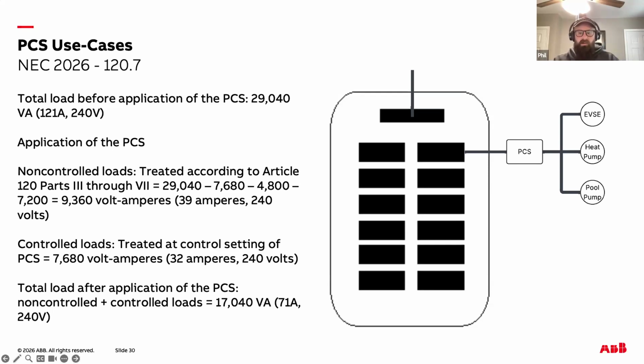Because the PCS is providing overload protection for this branch circuit, and per NEC requirements it cannot exceed 80% of the OCPD rating, the qualified person sets the PCS limit at 32 amps, which is 80% of the 40 ampere breaker. Since the PCS is monitoring only the controlled loads on this branch circuit, the NEC requires that these loads be represented in service load calculations using the PCS control setting rather than their individual nameplate ratings. As a result, the EVSE, pool pump, and HVAC heat pump are collectively treated as a 32 ampere controlled load for calculation purposes, rather than the much higher sum of all of their individual ratings.